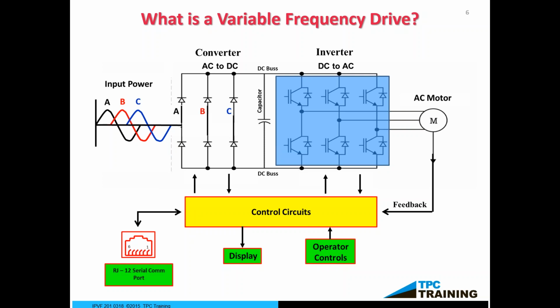As we move through the circuit, you can see that the AC to DC on the converter side, and then it goes DC to AC on the inverter side. And those 6, let's call them IGBT. So if you've drawn this system, mark an arrow there at the blue section. It's kind of a long word, and not to worry about it. It's an insulated gate bipolar transistor. Don't get caught up in the words or the symbology on that. It's nothing but a big giant switch. So what we do on this variable frequency drive is we take AC, we convert it to DC, and then we convert it back to AC.